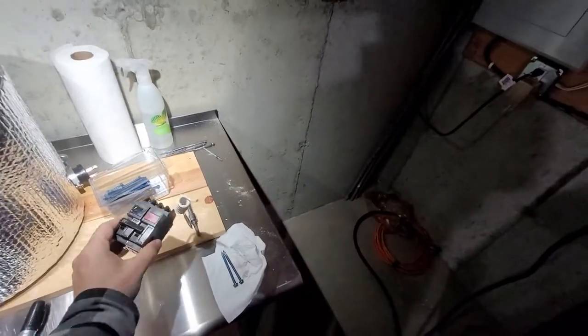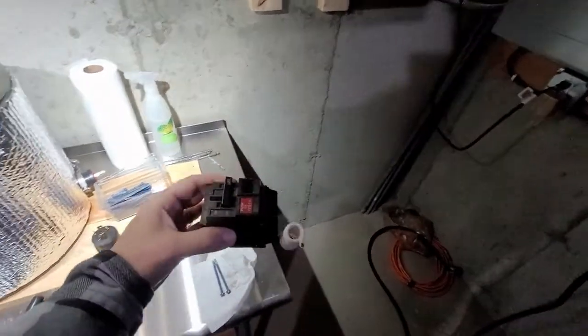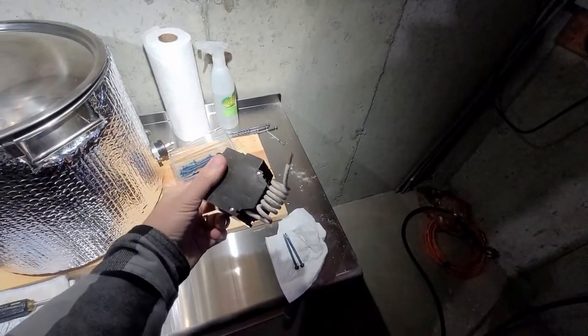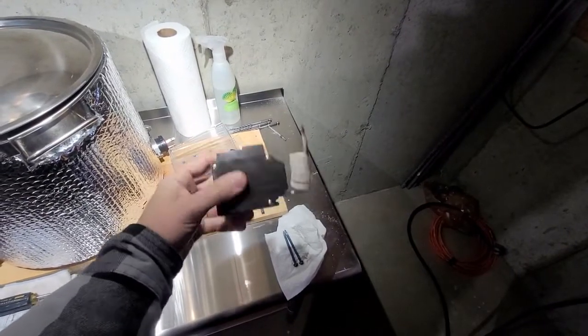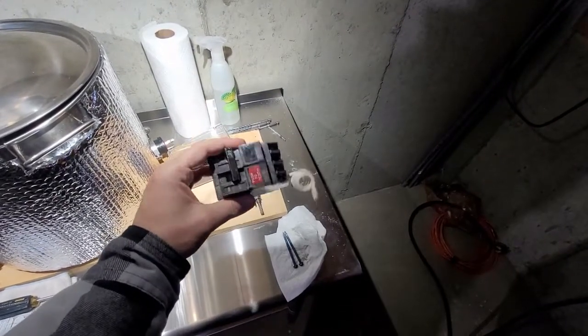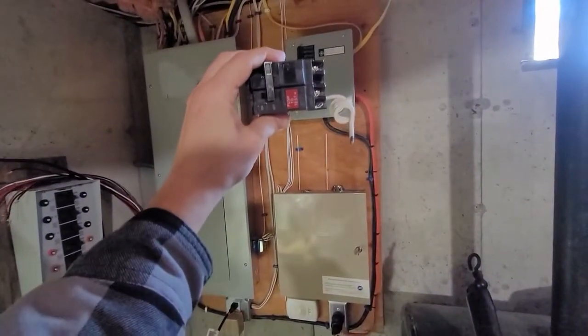But right now I just have a standard double pole breaker in there. I have to install one of these - this is what is called a GFCI breaker here. This will trip a lot quicker than a standard 30 amp if it really sees a ground fault. So I'm going to have to install this first before I use it with the brewery. I'll just replace that one double pole 30 amp.